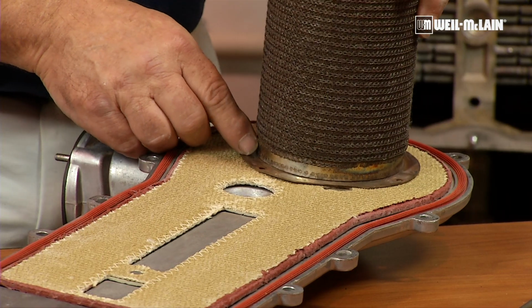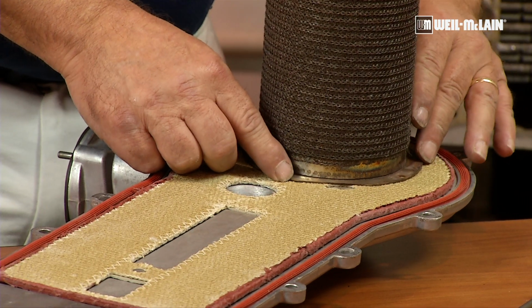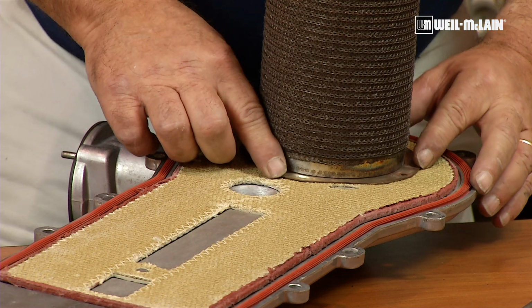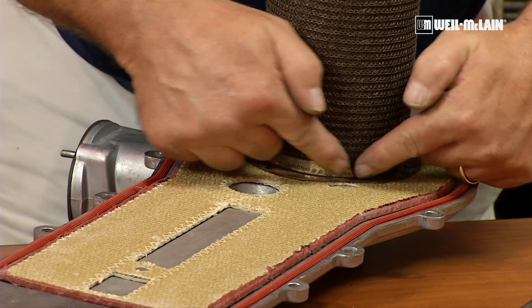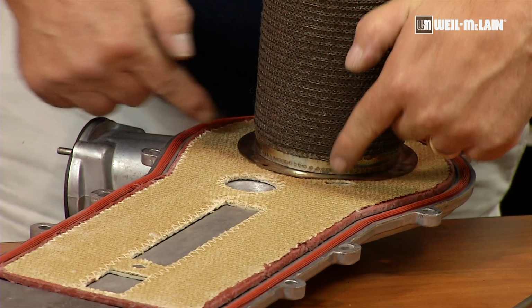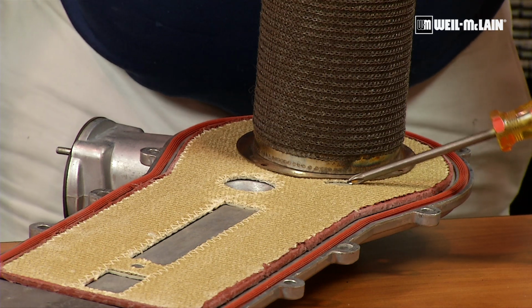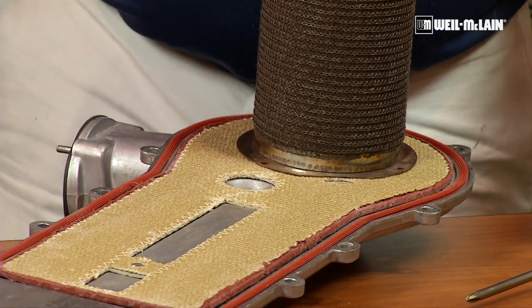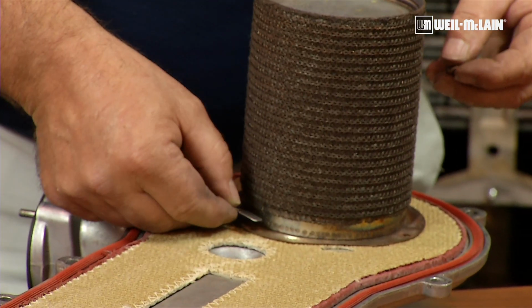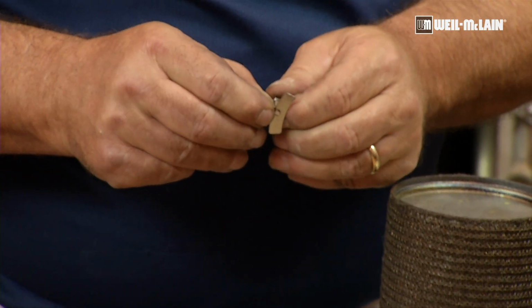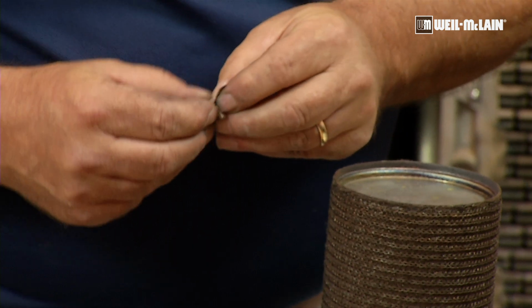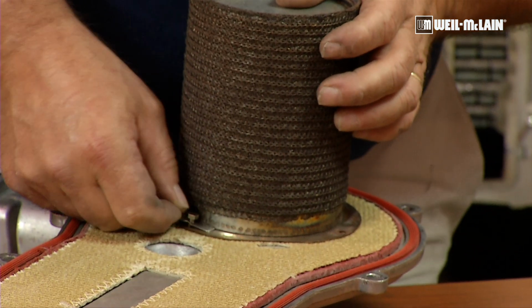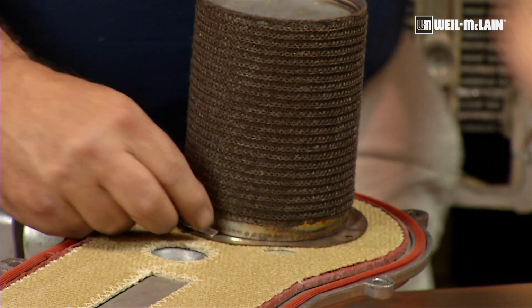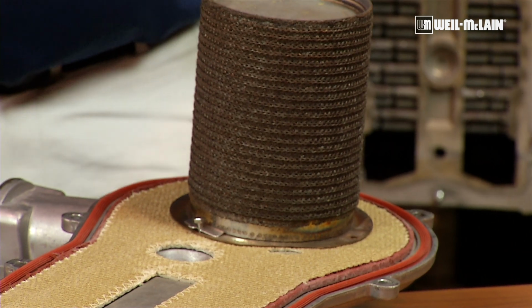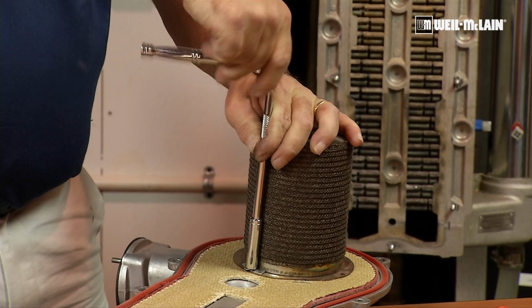Put the burner back on the new insulation, line it up with the holes, and again, the flat spot in the flange is oriented where the igniter would go through. You put the screw keeper down and the bolt goes through it. And then you put it in the hole. And gently tighten that bolt down.